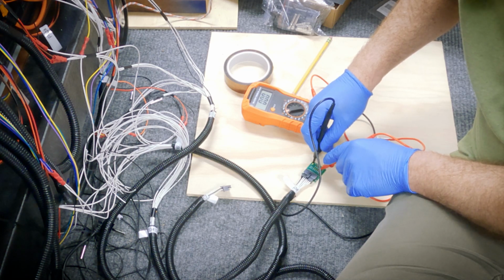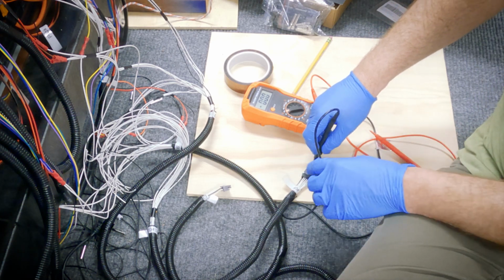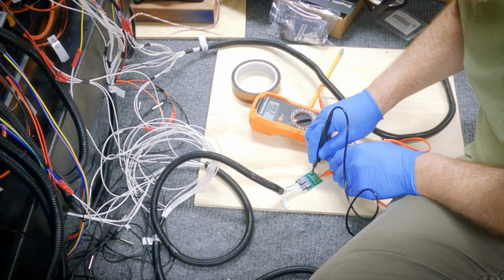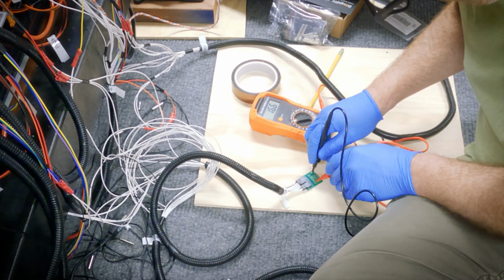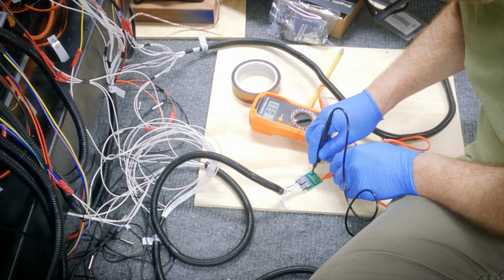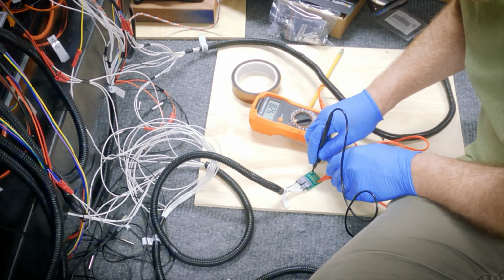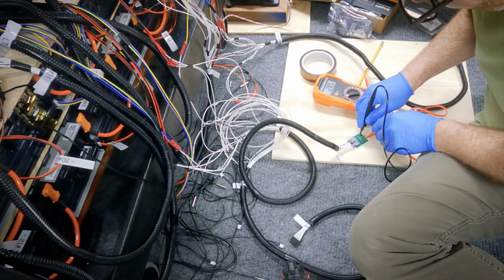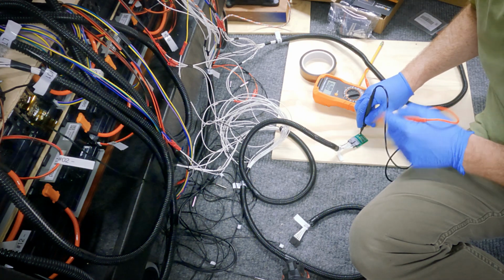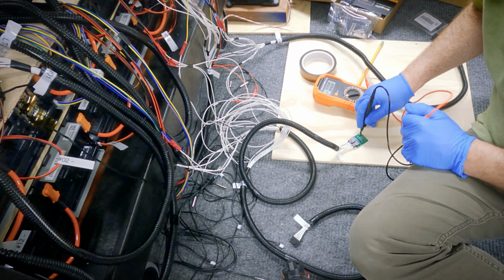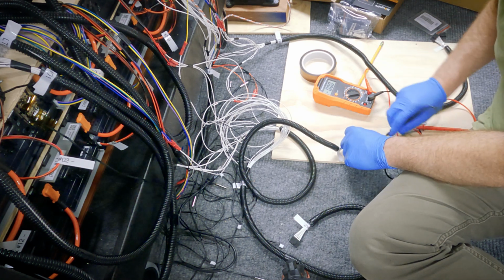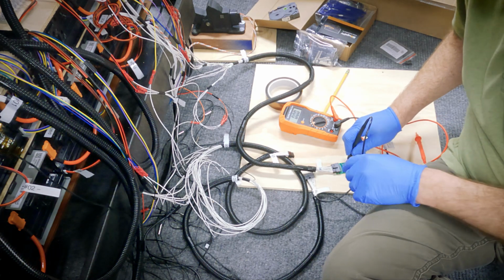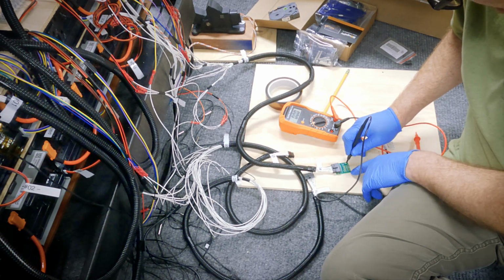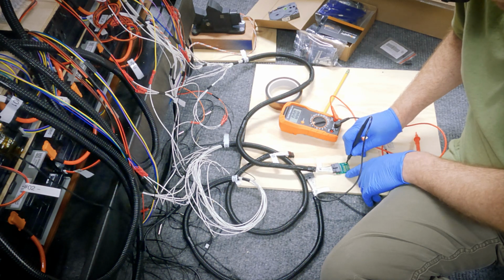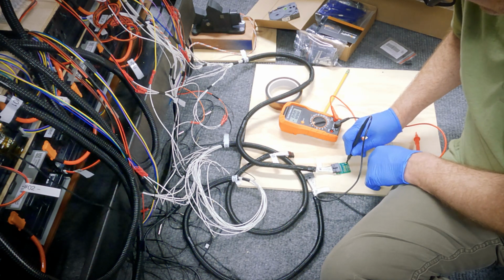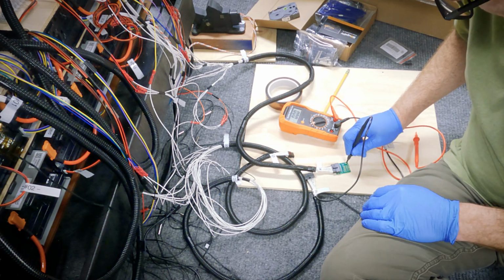Why is 8 reading 0? That's not good. 28, no, that's right. 32, 35, 39, 42. Yeah, that is right. So the point is it should go up by about 3.5 volts for each cell in order. I don't think there's anything wrong with the battery because 9 through 12 are exactly what they're supposed to be. It's only cell 8 on this LTC that has a problem.